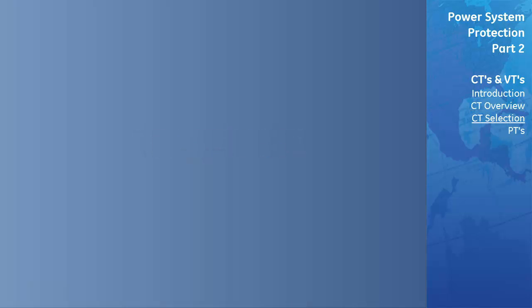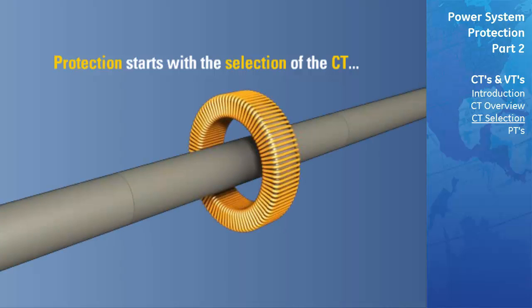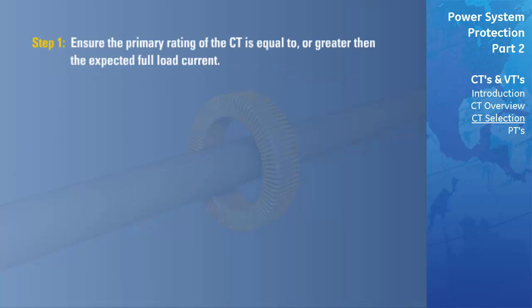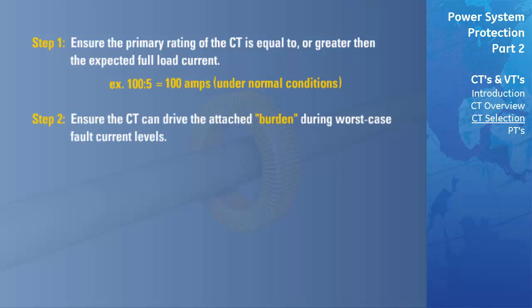Proper protection starts with the selection of current transformers. The following is a simple procedure that can be used to check whether or not there is the possibility of CT saturation. The first step is to ensure that the primary rating of the current transformers is equal to or greater than the expected full load current. We can determine the primary rating of a CT by looking at its ratio — for a ratio of 100 to 5, a CT has a primary rating of 100, meaning that no more than 100 amps should be passed through the CT under normal operating conditions. The second step is to ensure that the CT can drive the attached burden at the worst case fault current levels without saturating.